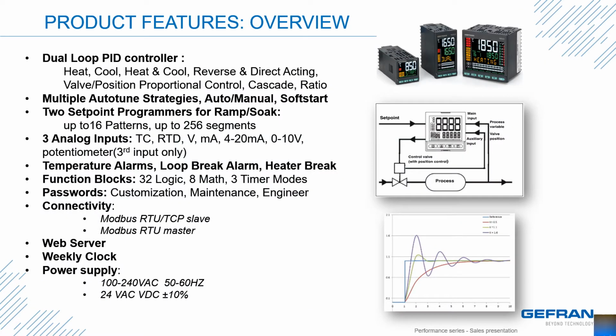There are a lot of features and abilities in the Performance Series, enough that I'll probably miss a few. All the units are capable of 1 or 2 PID loops. They can be configured as heat, cool, or heat cool. You can set up the unit to be a valve positioner, create cascade control loops or ratio control. You can easily change the unit to reverse acting or to direct acting outputs as you need.